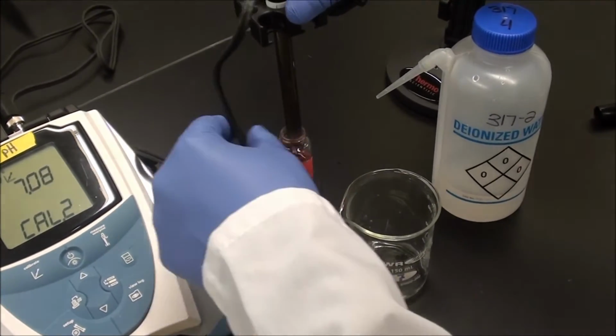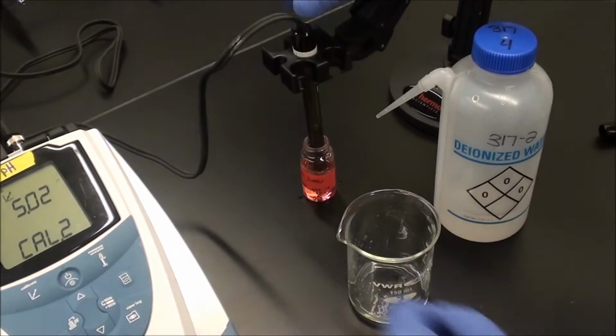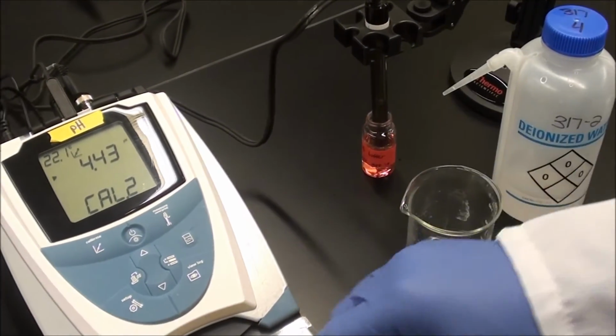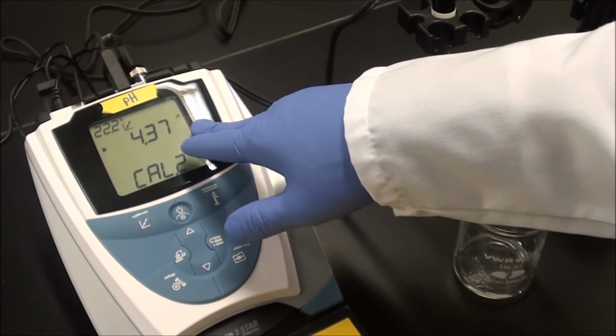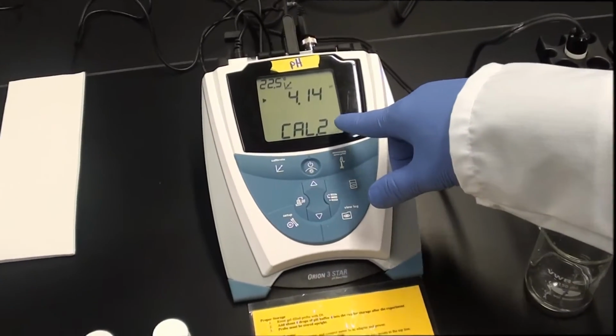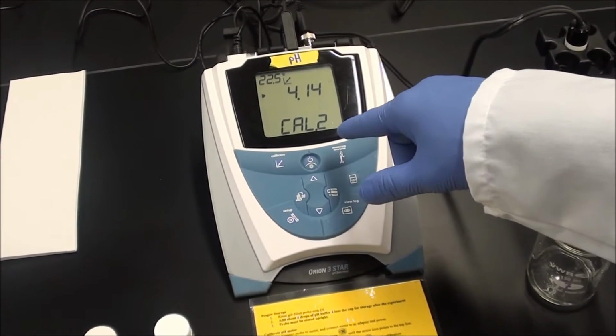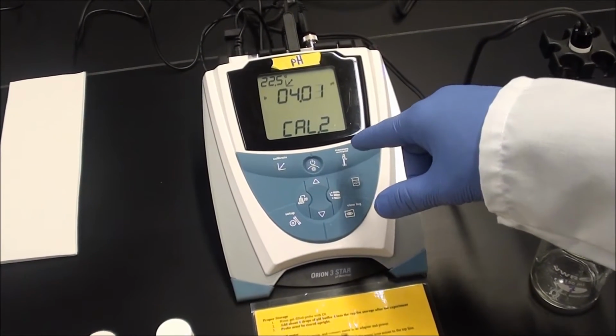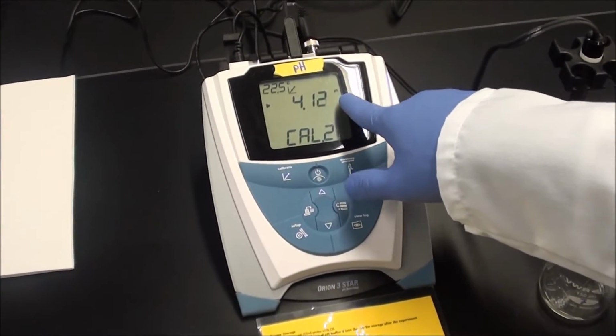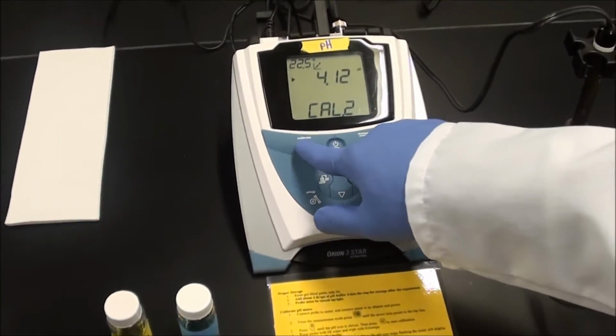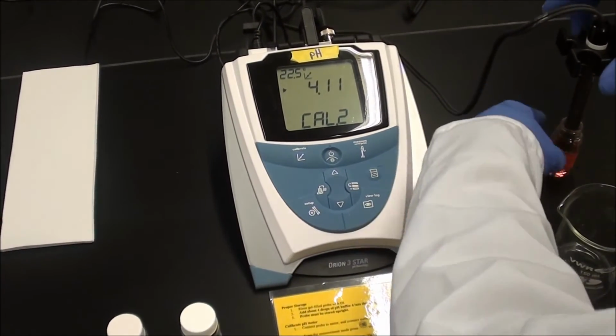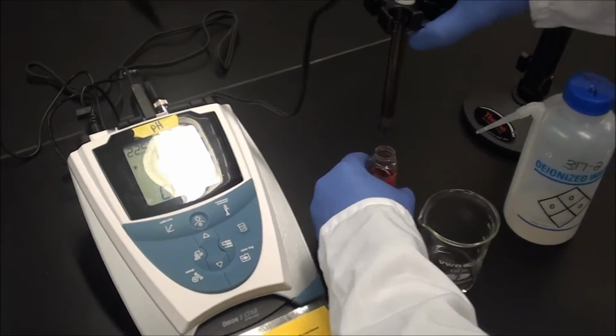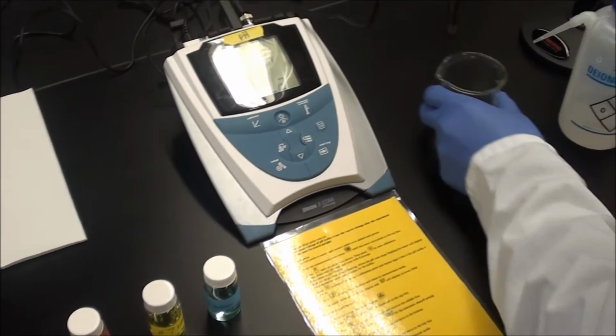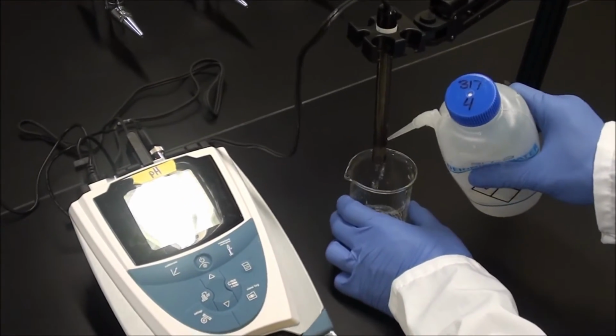And submerge it all the way down. And just as with the pH of 7, you wait until the pH stops flashing to proceed to the next. So again, when the pH icon stops flashing, the meter will display the temperature corrected pH value for the buffer. Once the pH has stopped, you're going to go ahead and push the calibrate button once again. Take out your probe from the pH buffer 4, cap it, put it into place, and you want to rinse the pH probe with DI water again, and make sure to wipe it with some clean Kim wipes.